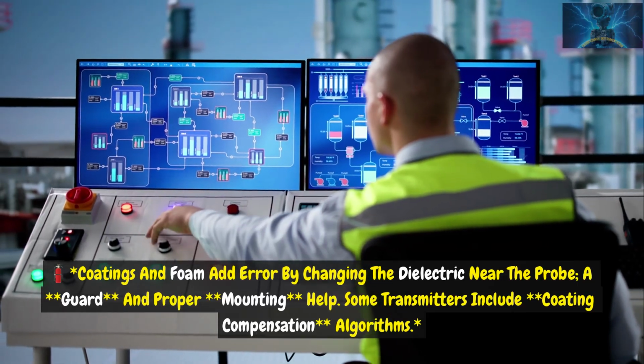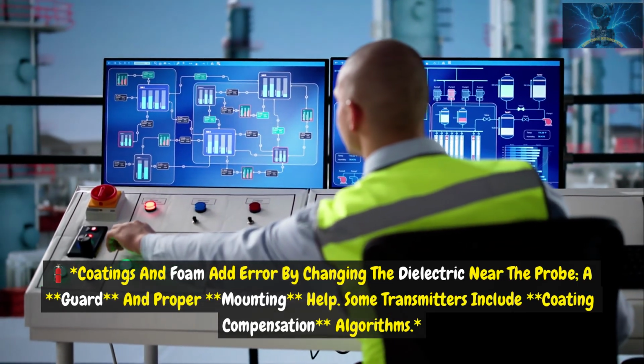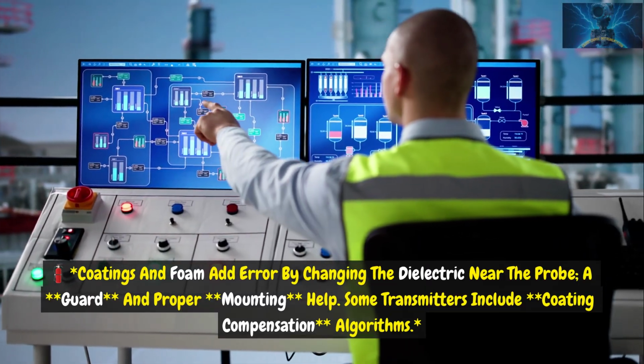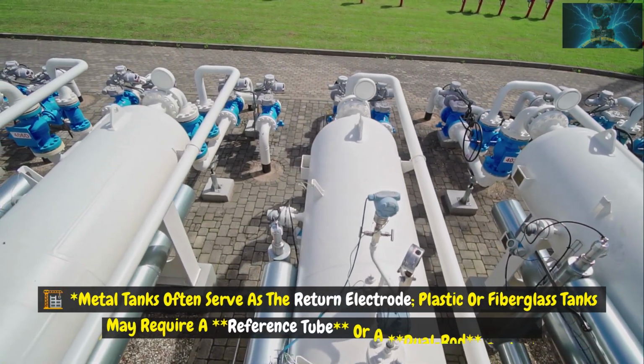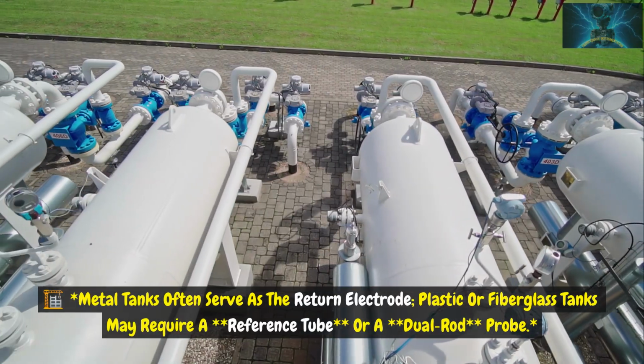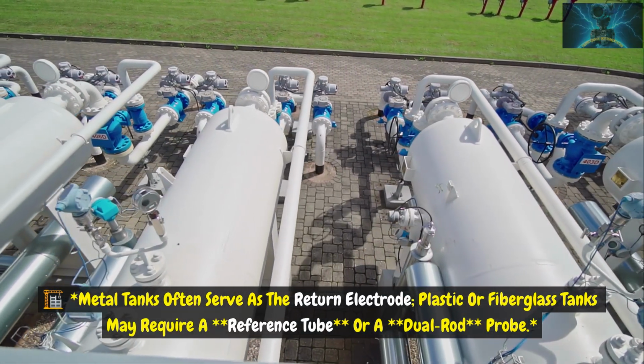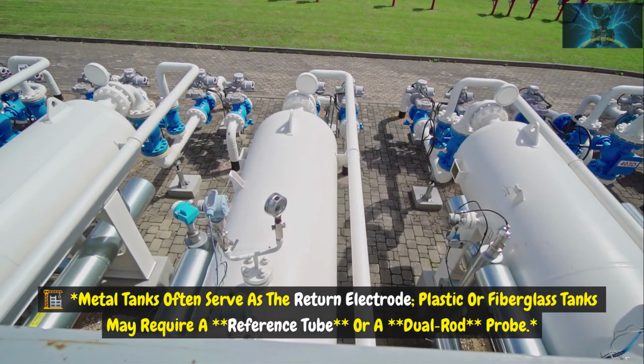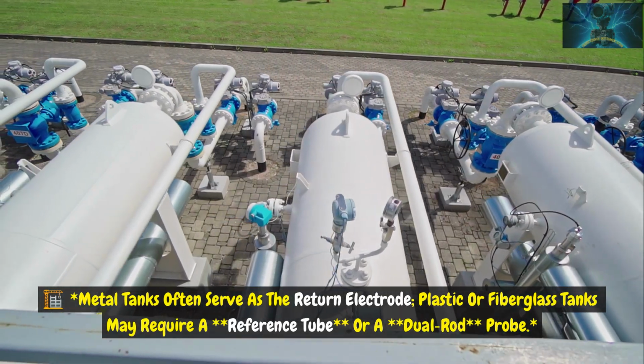Some transmitters include coating compensation algorithms. Metal tanks often serve as the return electrode. Plastic or fiberglass tanks may require a reference tube or a dual rod probe.